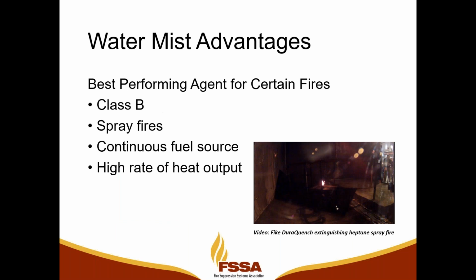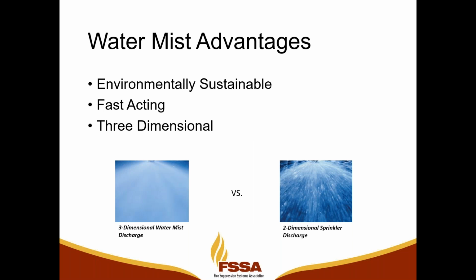Another big difference between water mist and sprinklers is that water mist systems are three-dimensional versus a sprinkler that's purely two-dimensional. So a water mist system is three-dimensional in very much the same way that a gaseous agent system is three-dimensional. Jonathan mentioned the way that these sub 1,000 micron droplets entrain themselves in the convection currents in the space that we're protecting during a fire. And those convection currents draw the water mist to the fire and let it do its job. So if we've got a fire in a concealed space, maybe underneath a horizontal surface like a desk or a table, the water mist is actually going to penetrate those concealed spaces and do its job.